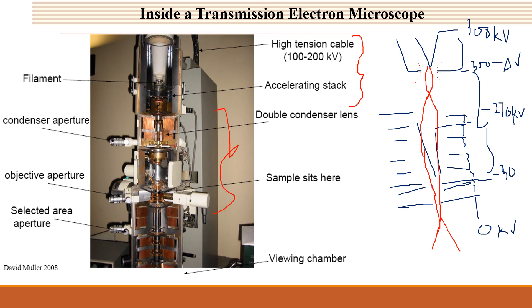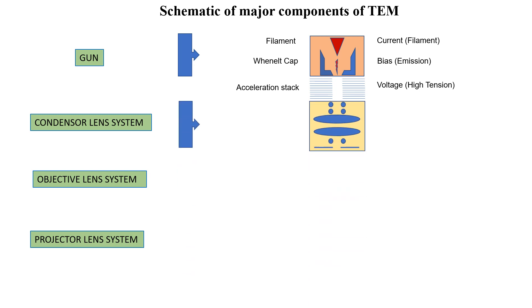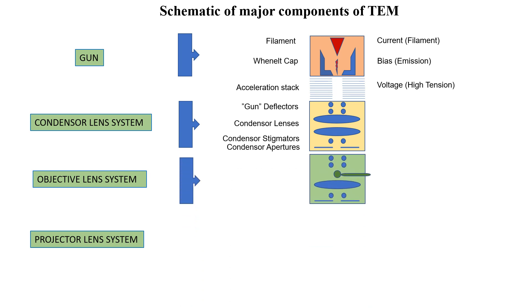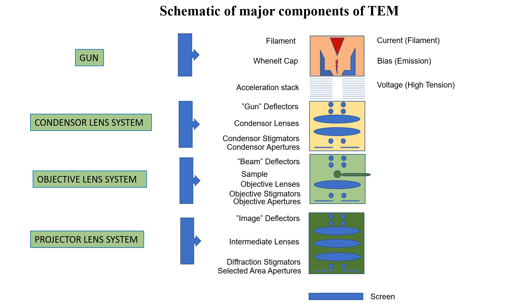The Wehnelt cylinder is an electrostatic lens, while the condenser and objective lenses are electromagnetic lenses. The major components of the TEM are: the gun system (filament, Wehnelt cap, acceleration stack); the condenser lens system (gun deflectors, condenser lenses, condenser stigmators, condenser apertures); the objective lens system (beam deflectors, sample, objective lenses, objective stigmators, objective apertures); and the projector lens system (image deflectors, intermediate lenses, diffraction stigmators, selected area apertures, and finally the screen).